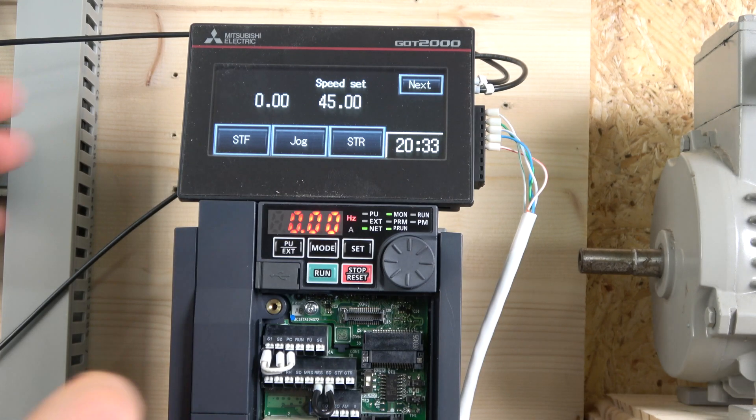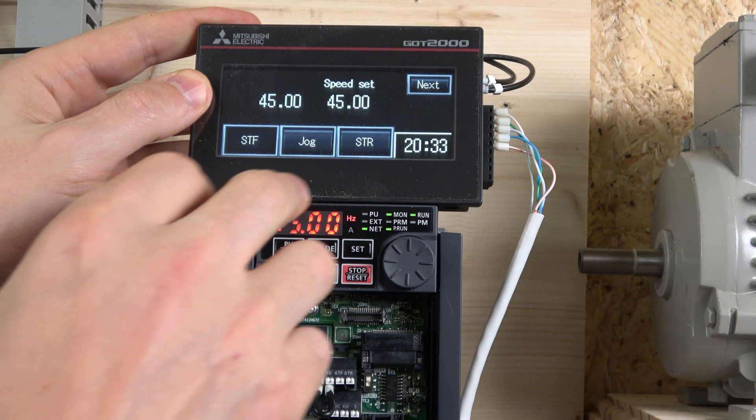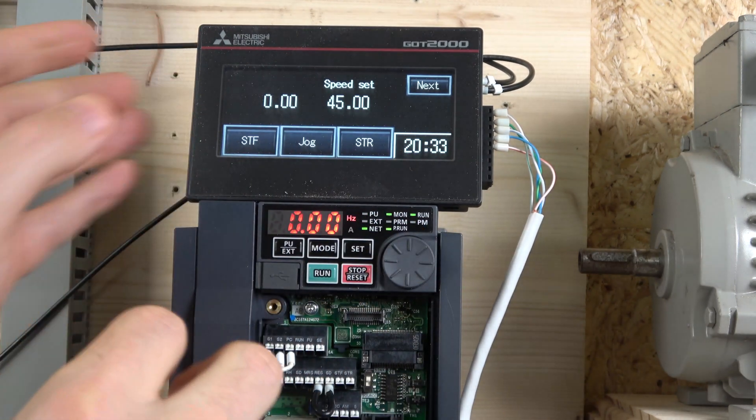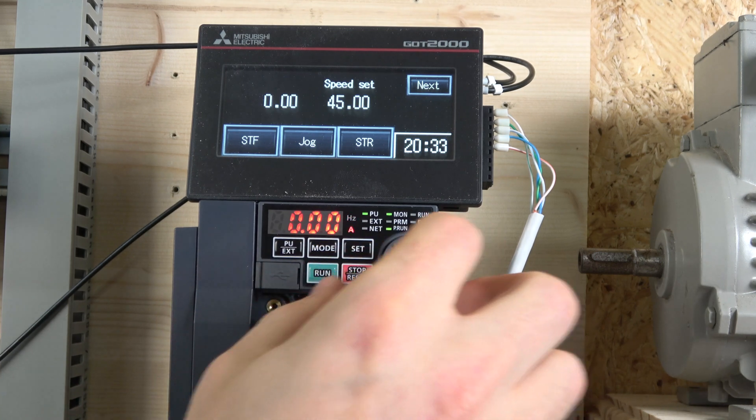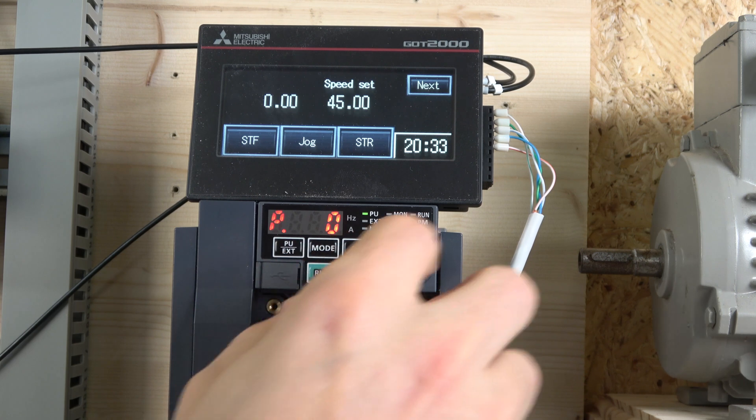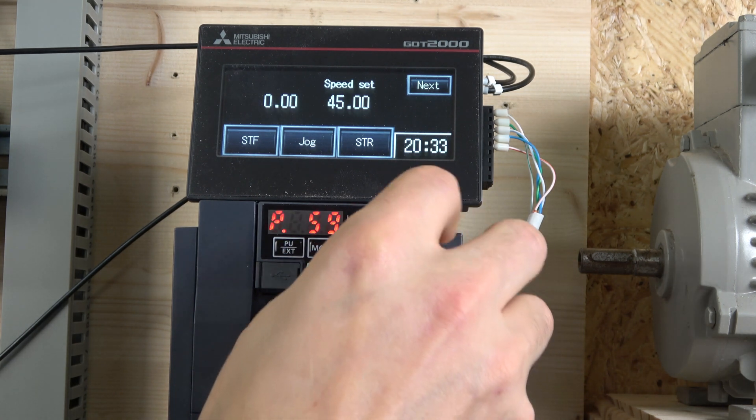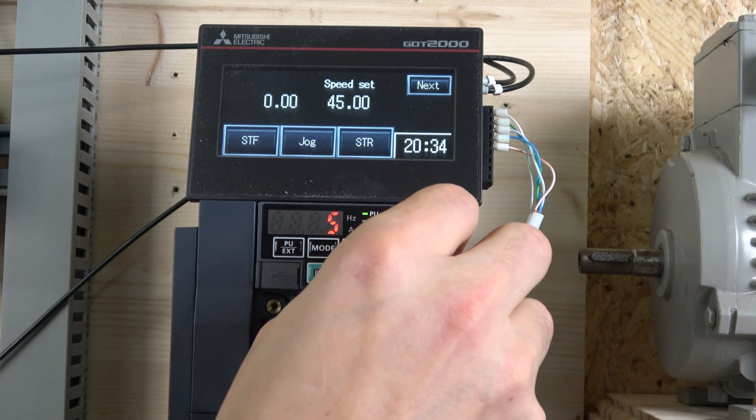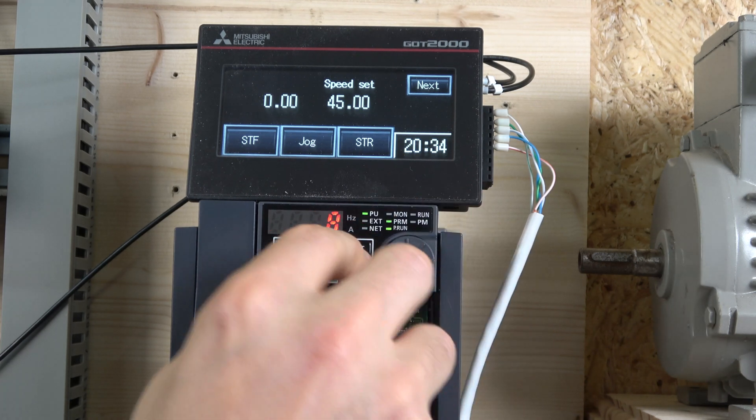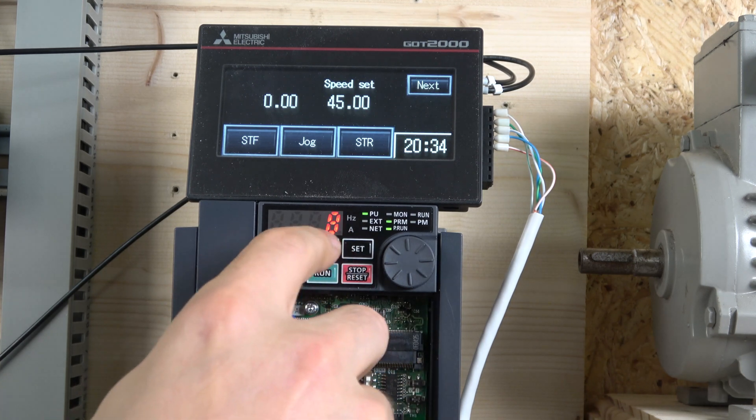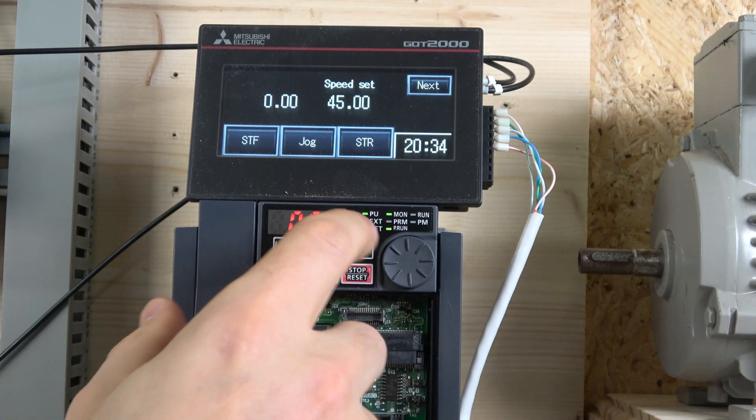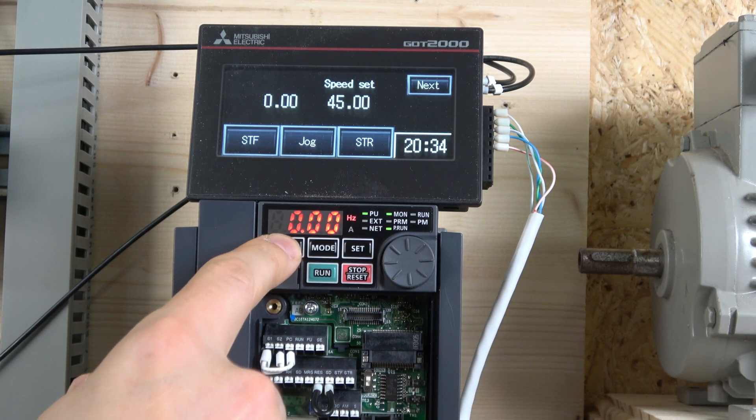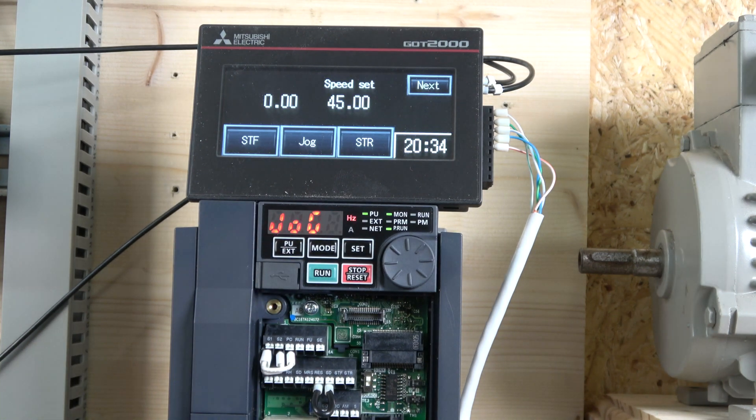Here we are. Let's check it out what we have created. Let's start up. Oh, that's an awful sound. One second. What we're going to do is jump to PU mode, go to parameter 72, which is our carrier frequency. Let's change that to make that sound go away. We're going to change that to about 8. That'll be perfect.